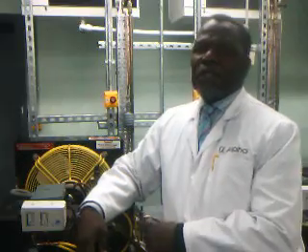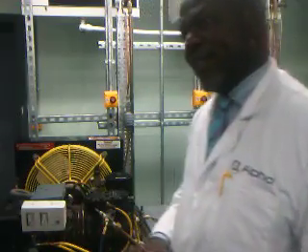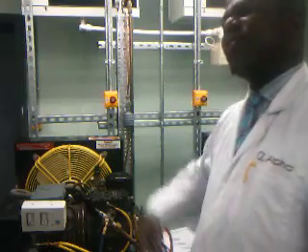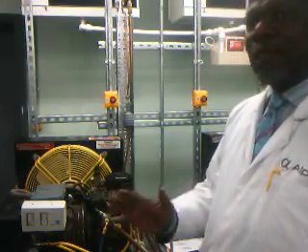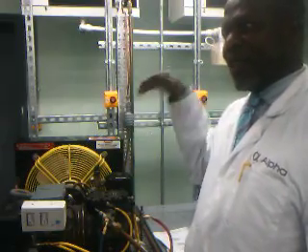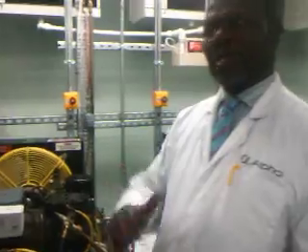How do we know how much to recover? It's very difficult to determine how much to recover. But what you do is recover in small quantities. You just take small, like 200 grams, and look at the reaction of the system. Wait for about 10 minutes, let it run, let it settle, check again. If it's still high, then you recover maybe 500 grams, and then you check again.